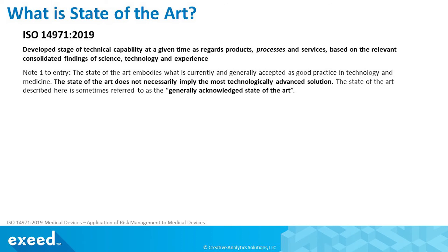Let's look at the definition, a few examples, and three key points important for this term. ISO 14971 defines state-of-the-art as the developed stage of technical capability at a given time as regards products, processes, and services based on the relevant consolidated findings of science, technology, and experience. An important clarification note states that the state-of-the-art embodies what is currently and generally accepted as good practice in technology and medicine, and it does not necessarily imply the most technologically advanced solution. It is sometimes referred to as the generally acknowledged state-of-the-art.